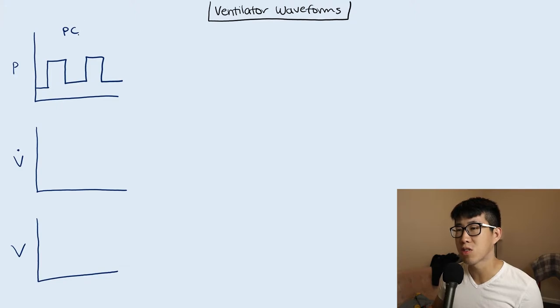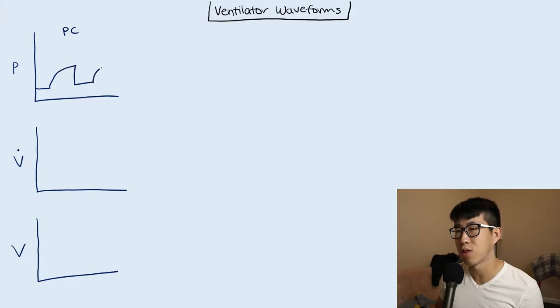If you're in volume control mode, then it's going to look slightly different. It's going to have a little bit more of this kind of shark fin appearance in volume control mode.